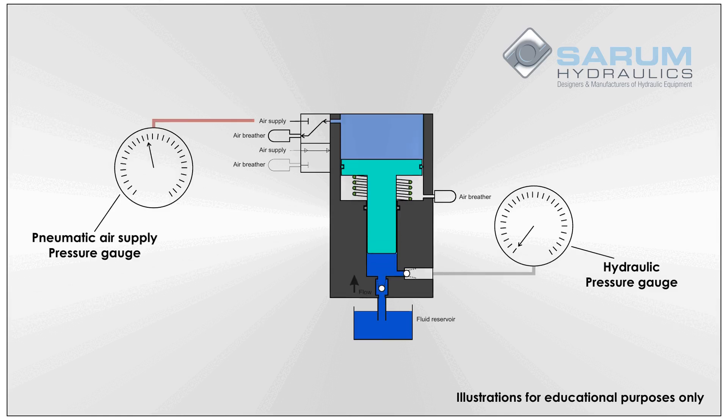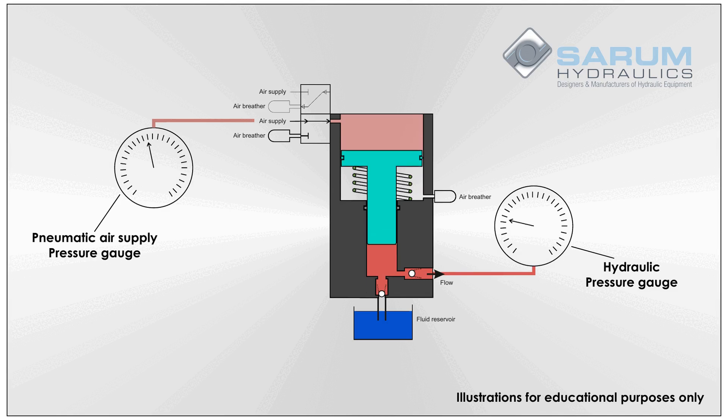The pump will then gradually start to cycle at a slower rate as the pressure in the receiver increases and offers more resistance to the reciprocating differential piston. The pumps stop automatically when the output pressure force and the air drive force is balanced to create a stall condition.